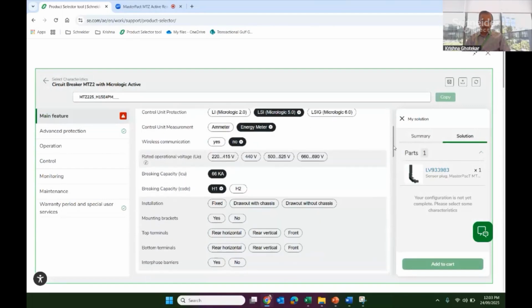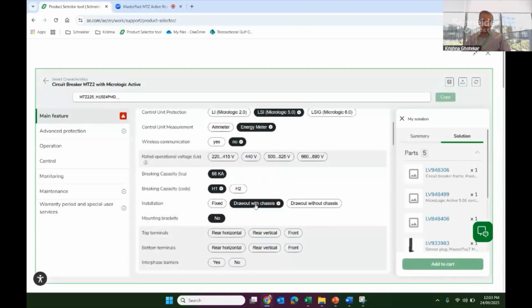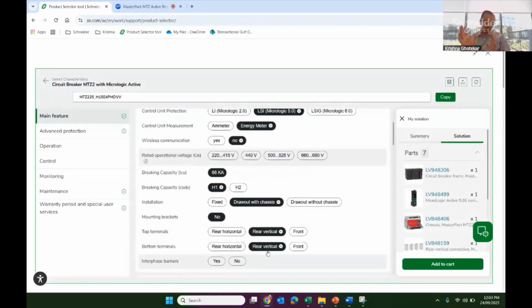So I want an H type breaker, let's say 66 kA breaker, fixed type, draw-out with chassis, which is our typical draw-out breaker. Or you can have draw-out without chassis, which means you can order the chassis separately and only the moving part of the breaker separately. Let's say draw-out with chassis and type of terminal: horizontal, vertical, front. Now with this, it makes my standard breaker without any accessories or other. So this will be the part number.